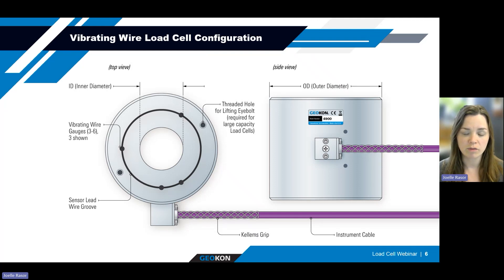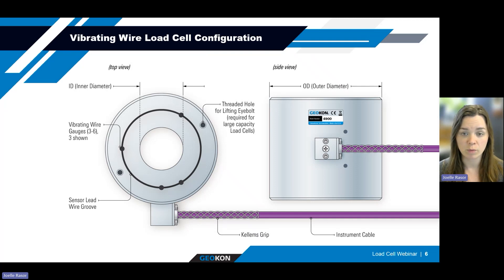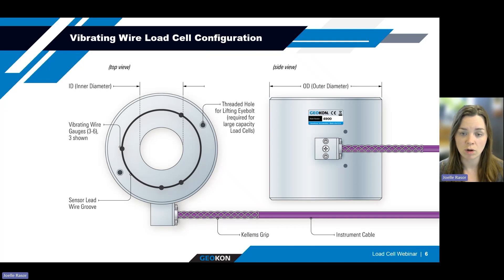Readings are taken from each strain gauge and are averaged. These readings can be used in conjunction with the calibration factor to calculate the applied loads. The vibrating wire load cell is provided with an integral thermistor for monitoring temperature. If the load cell will be installed where it will experience varying temperature, it is recommended that temperature corrections be applied to the final calculations. The dimensions of the vibrating wire load cell will vary depending on the required capacity, and these load cells are typically manufactured to order. Depending on the size, it can be provided with threaded holes for lifting eyes on top.